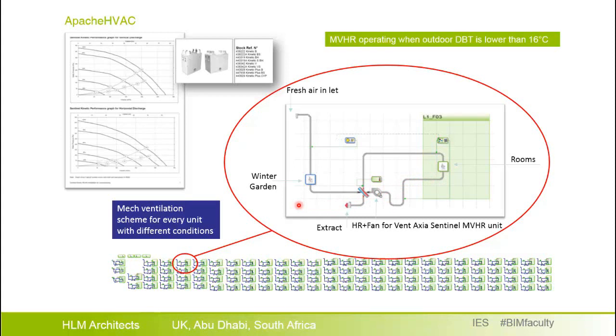This is a very simple network scheme, but Apache HVAC allows very detailed settings using manufacturer data, so the results are very accurate. Since every winter garden is different in its position and solar radiation, we set a specific network scheme for every unit. This system is complementary to the windows system in a sort of mixed mode operation, meaning it kicks in whenever the outdoor temperature is too low — more or less below 16°C.